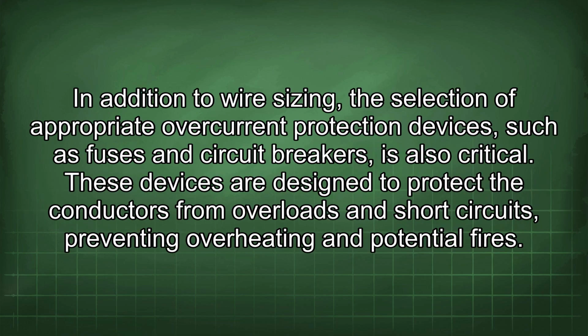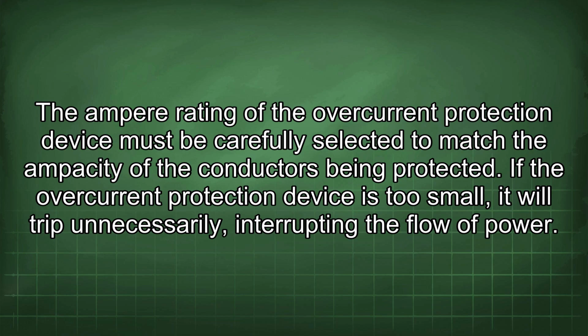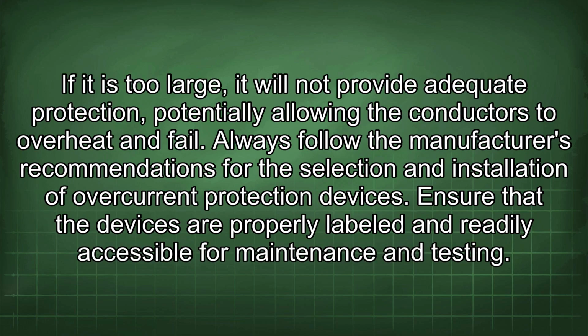In addition to wire sizing, the selection of appropriate overcurrent protection devices, such as fuses and circuit breakers, is also critical. These devices are designed to protect the conductors from overloads and short circuits, preventing overheating and potential fires. The ampere rating of the overcurrent protection device must be carefully selected to match the ampacity of the conductors being protected. If the overcurrent protection device is too small, it will trip unnecessarily, interrupting the flow of power. If it is too large, it will not provide adequate protection, potentially allowing the conductors to overheat and fail.